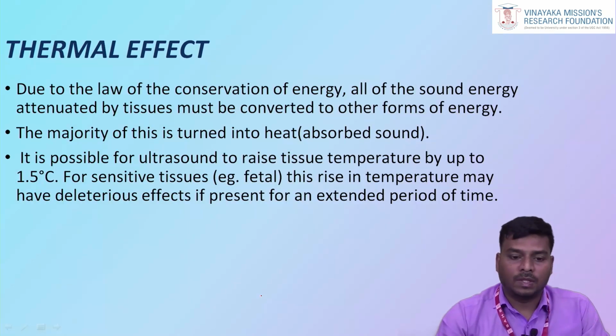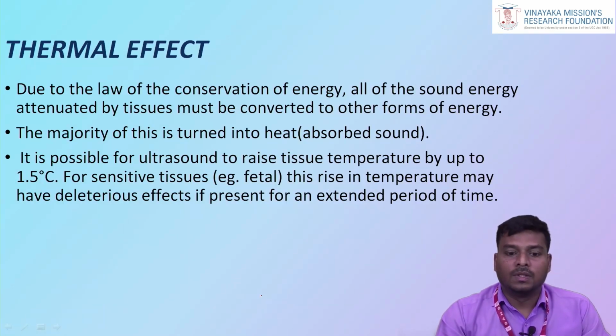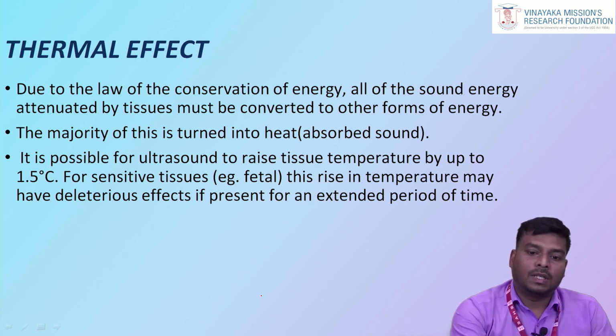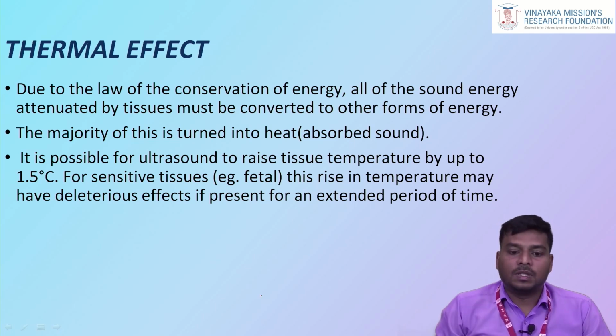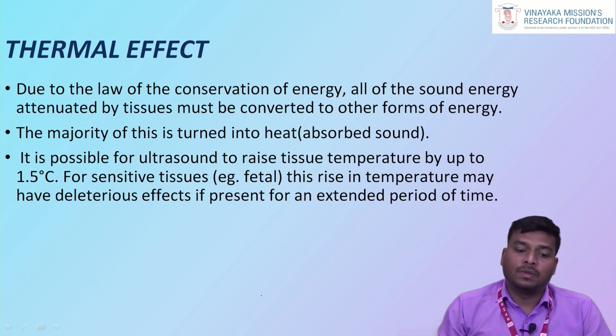We will discuss the thermal effect first. The majority of absorbed sound turns into heat. That absorbed sound producing heat is the thermal effect. Due to the law of conservation of energy, all the sound energy attenuated by tissues must be converted to another form of energy. It is possible for ultrasound to raise tissue temperature by up to 1.5 degrees Celsius, for sensitive tissues, for example the fetus. This raised temperature may have significant effects if present for an extended period of time.